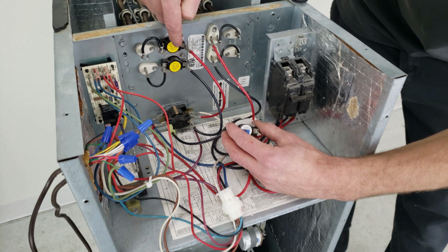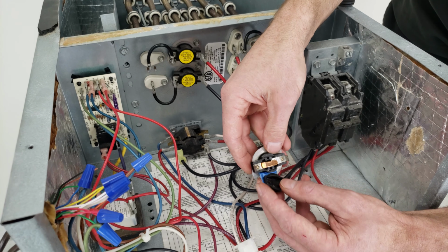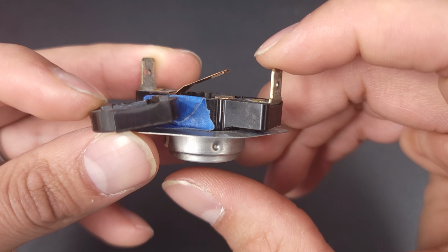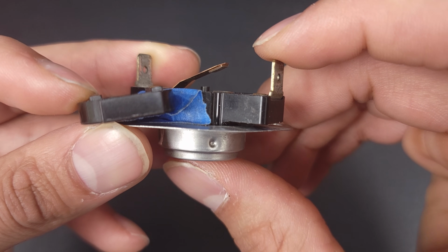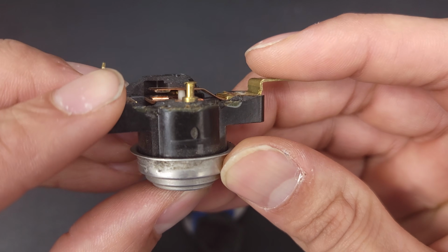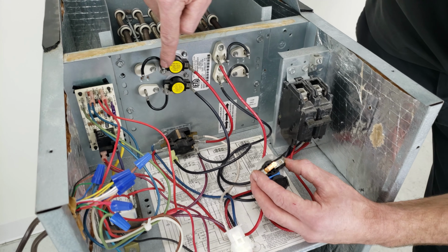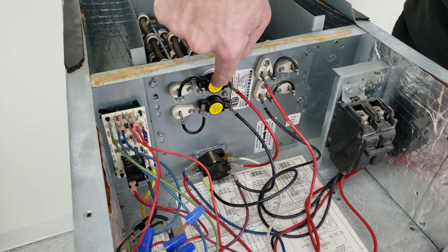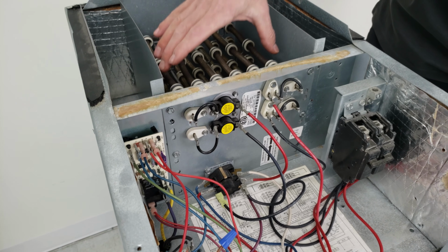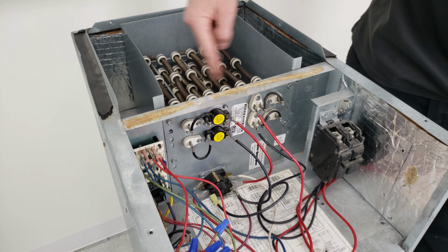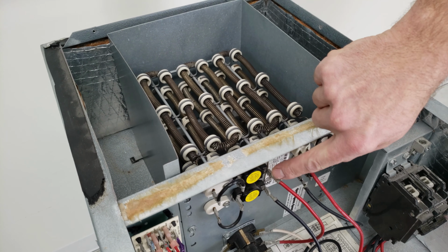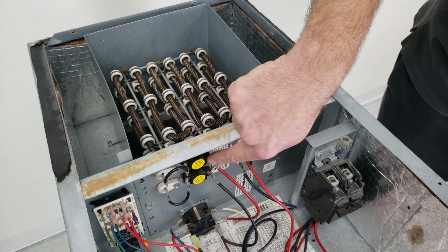Here's another example, these temperature sensors. On the inside, there is this contact, and then there's a little tiny rod on the inside. When this bimetal disc pops due to heat and flexes, these contacts are so small. This switch is going to have a lot of current crossing it when the electric strip heaters are running. Back here are the electric strip heaters. Those tiny little contacts could become pitted and then work sometimes and not work other times, depending on if it closes properly.